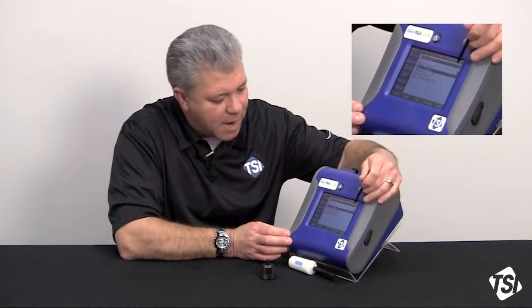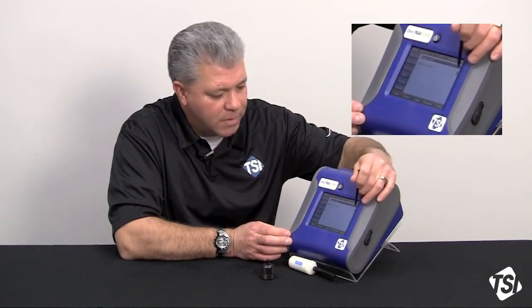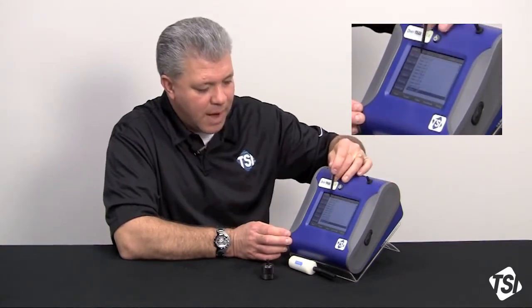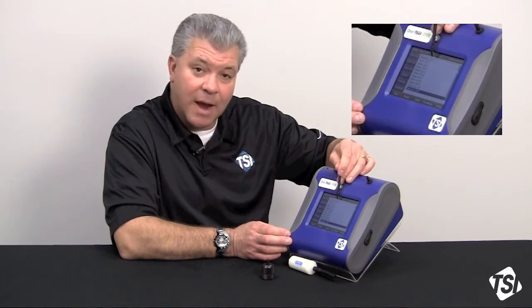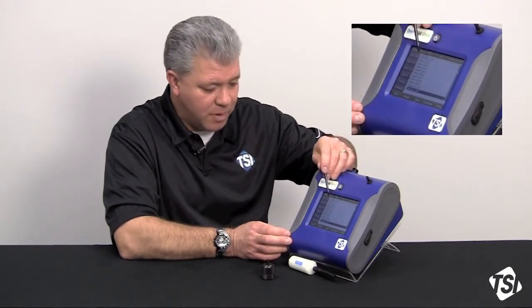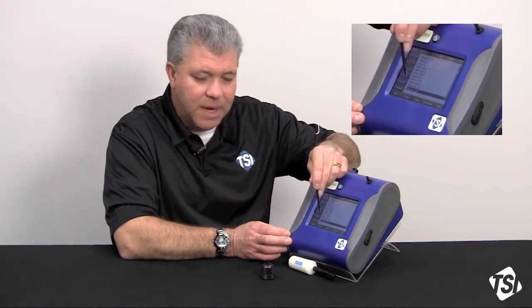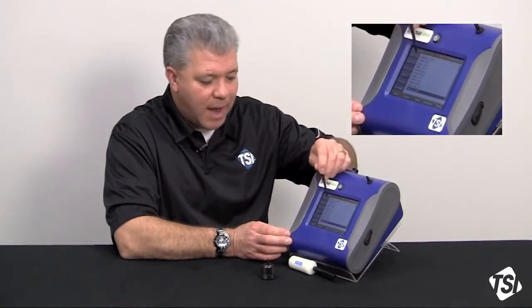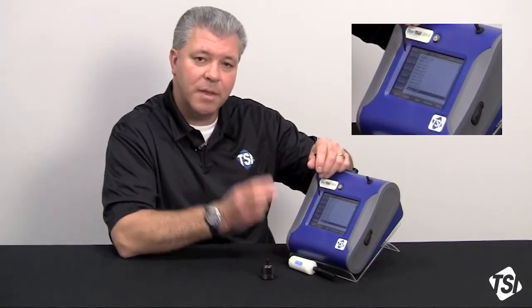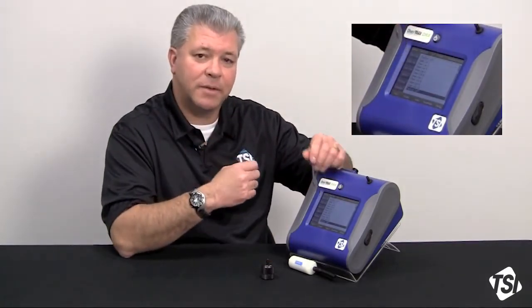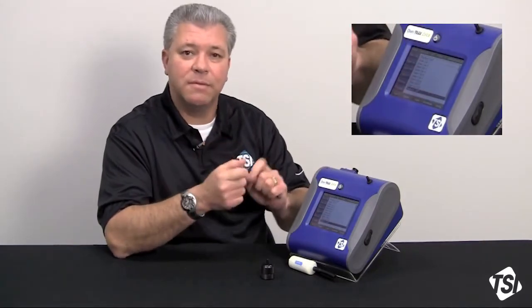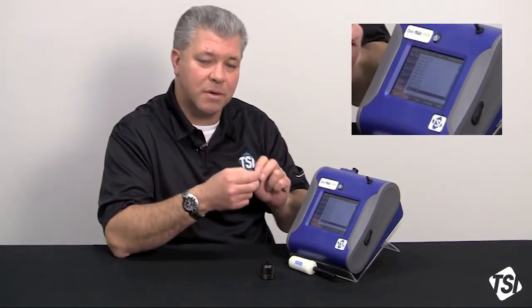Now, from the upper drop-down menu, the top one is factory cal. That's the factory calibration that was put into the instrument. And then there are 10 user calibrations. And in these user calibrations, there are two different correction factors. One is a photometric correction factor, and the other is the size correction factor.